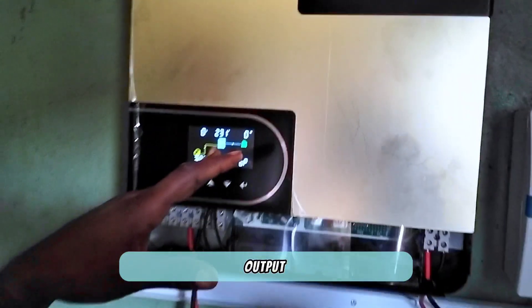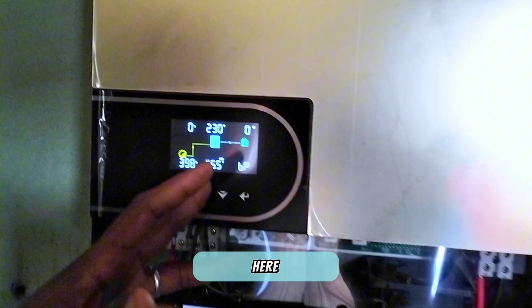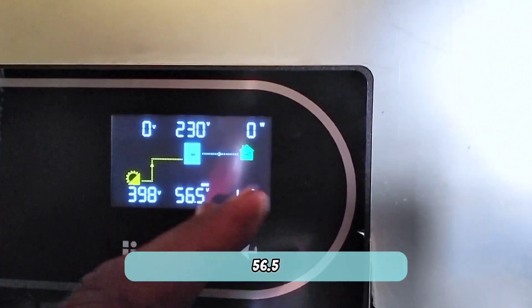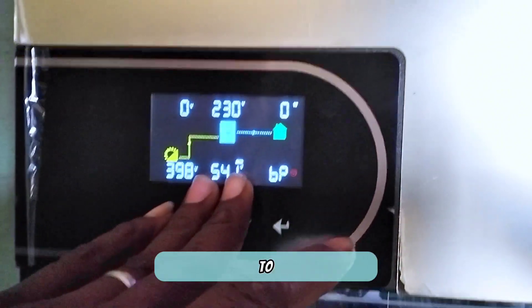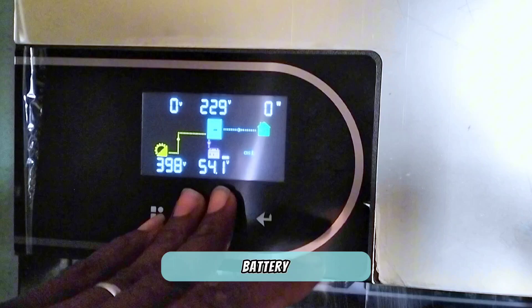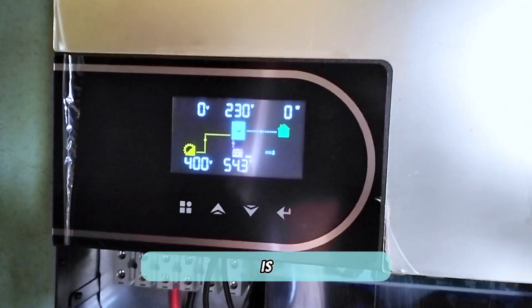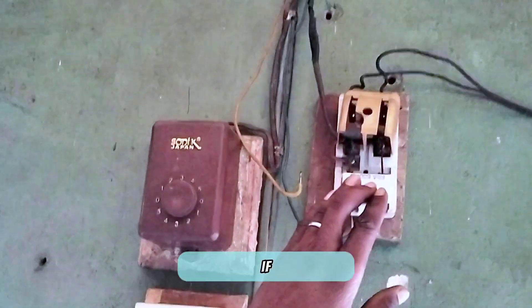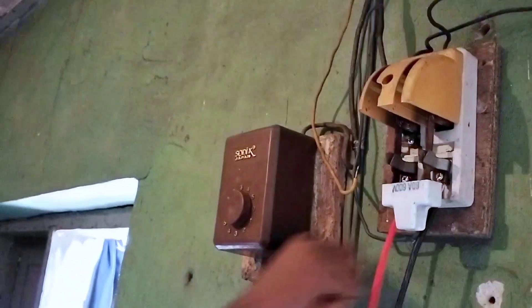You can see there is an output of 230 volts, and here it's showing 56.5 volts — it is converting from around 398 volts to supply this output, which would normally represent the battery side. Even though it's showing the battery path, the battery is not connected. We're going to turn the changeover down to see if it will power the loads.